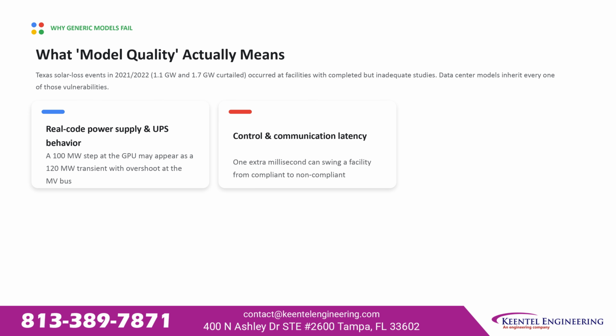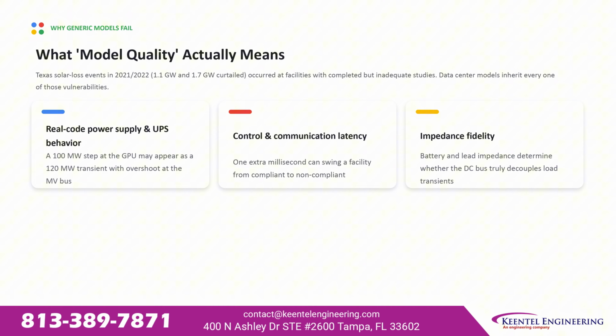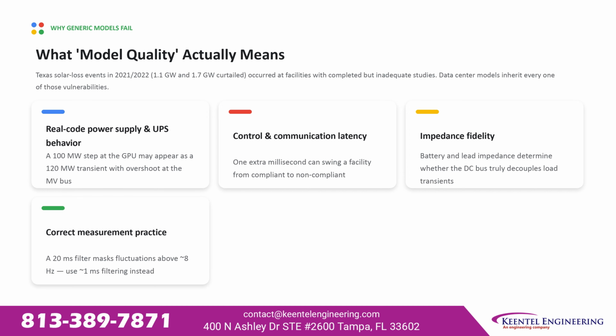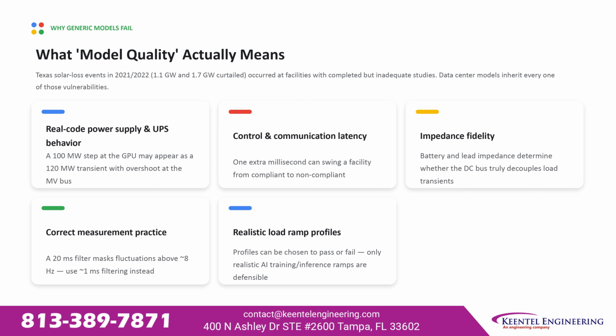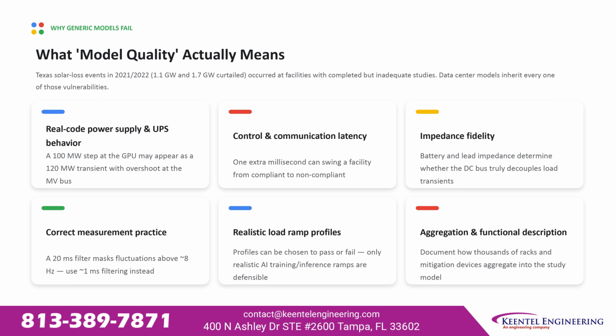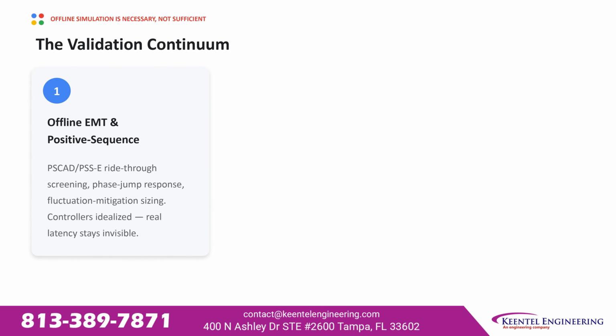1 extra millisecond can swing a facility from compliant to non-compliant. Impedance fidelity. Battery and lead impedance determine whether the DC bus truly decouples load transients. Correct measurement practice. A 20 millisecond filter masks fluctuations above roughly 8 Hz, so roughly 1 millisecond filtering is what's actually needed. Realistic load ramp profiles. A profile can be chosen to pass or fail a study, so only realistic AI training and inference ramps are defensible. And aggregation and functional description, documenting how thousands of racks and mitigation devices aggregate into the study model in the first place. Offline simulation alone isn't enough.